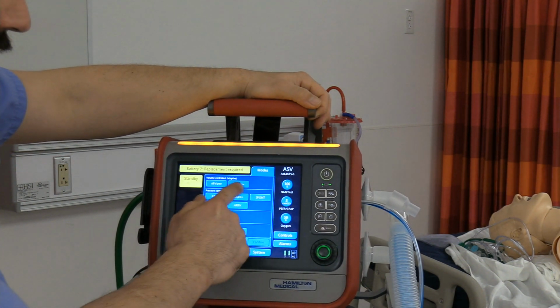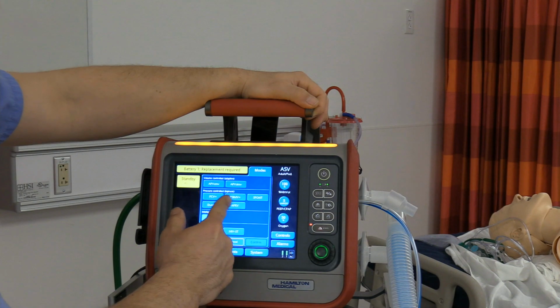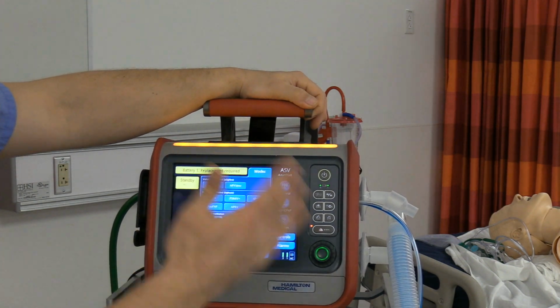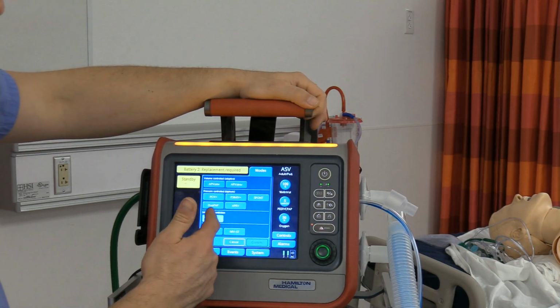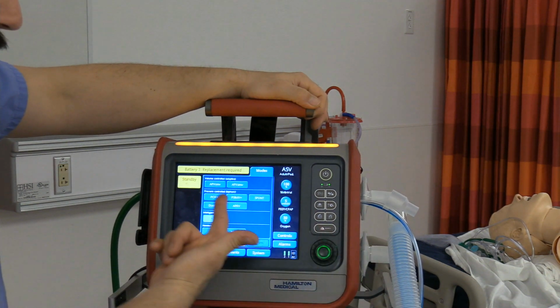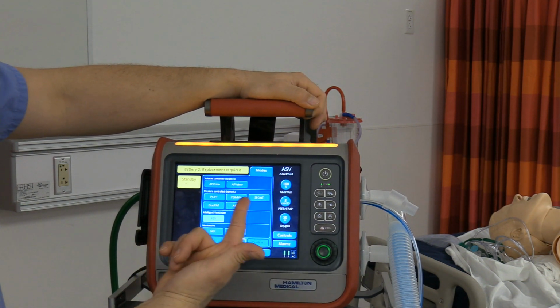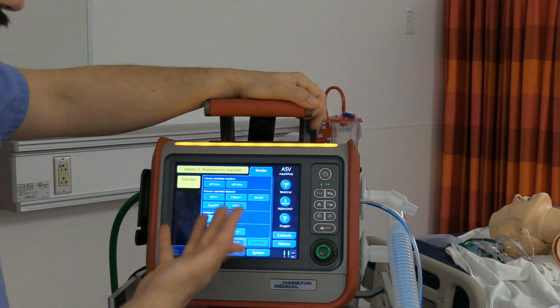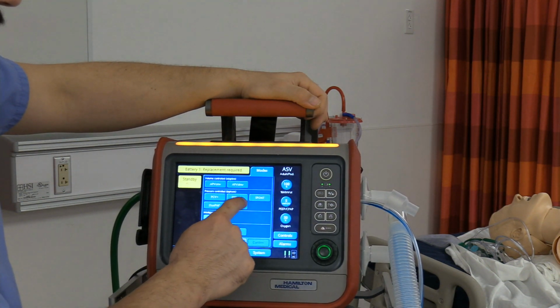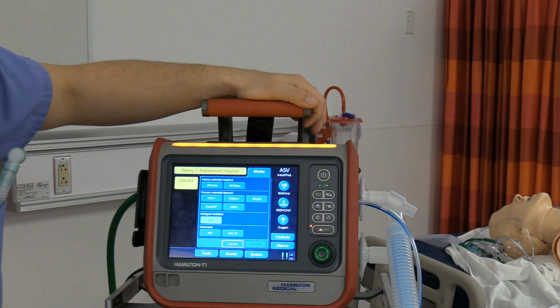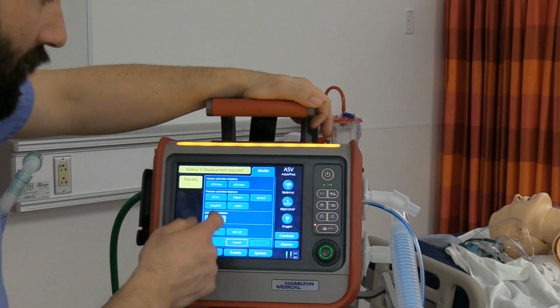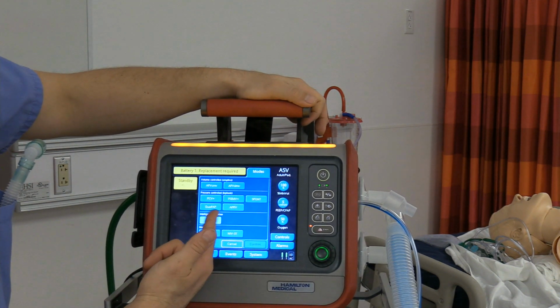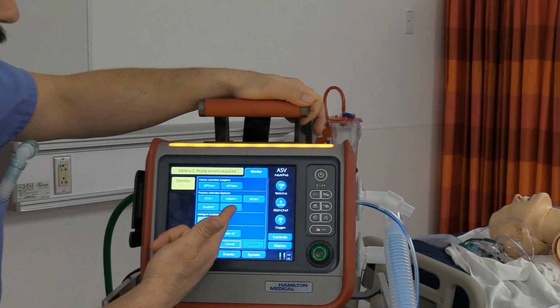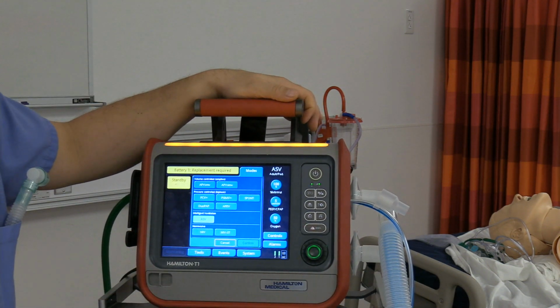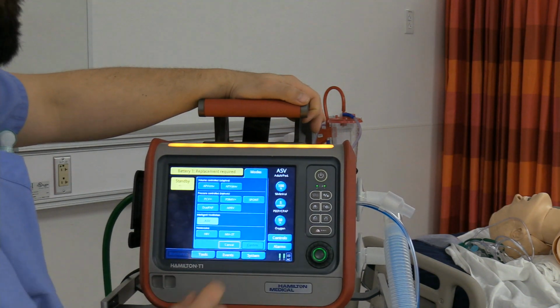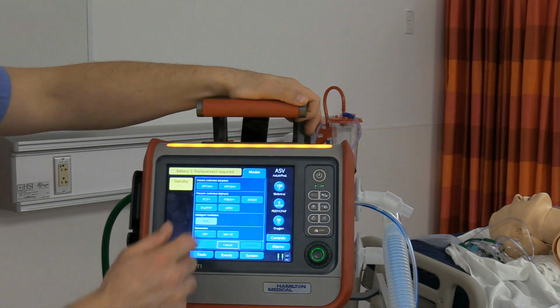So we've got our volume targeted pressure modes. We've got straight up pressure ventilation, so controlling pressure is a control variable in the traditional sense. That could be mandatory, like PCMV, which is typical pressure continuous mandatory ventilation, pressure assist control. We've got pressure SIMV, and spontaneous pressure support ventilation for the actively breathing patient. And then you've got two ways of running inverse ratio pressure control, so DuoPAP or APRV. DuoPAP is a little more familiar if you're coming from the 980 Puritan ventilator series.